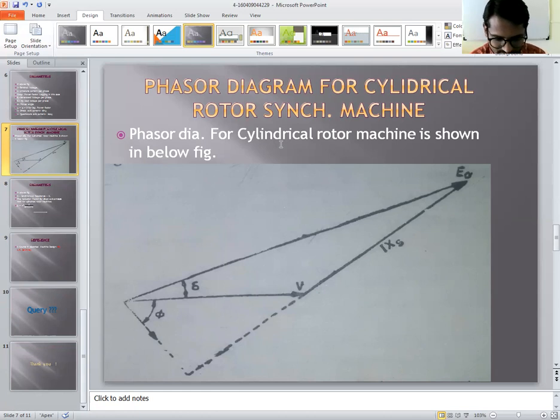After that, the alternator is driven by a prime mover and run at a speed close to the synchronous speed, but a little less than the synchronous speed. Record the maximum and minimum values of the current and voltage by ammeter and voltmeter connected in the stator circuit of the armature. We have to draw an observation table for that.